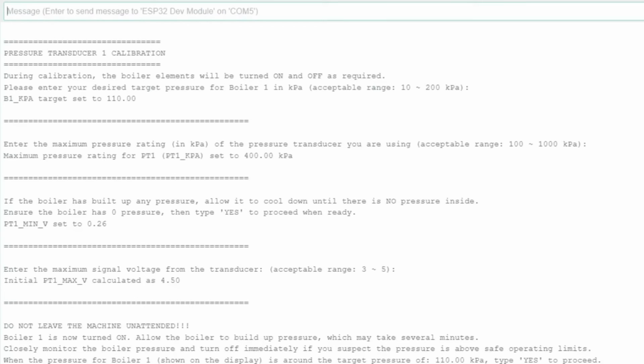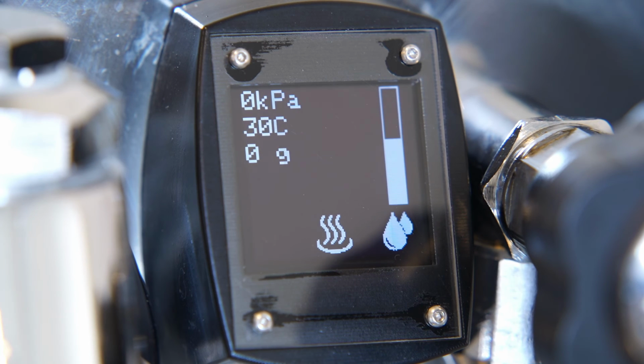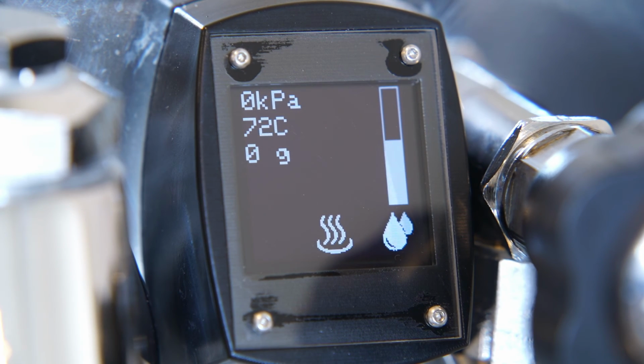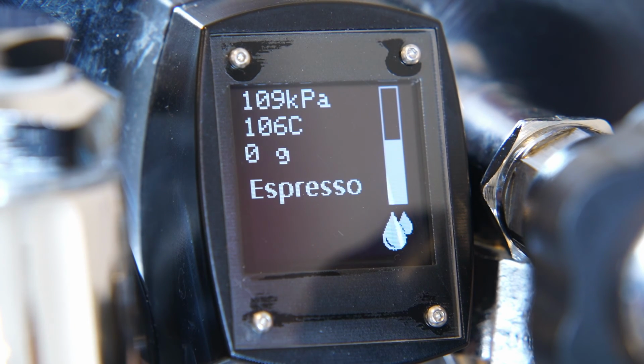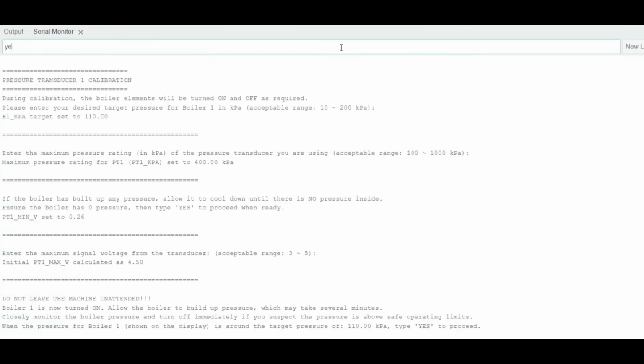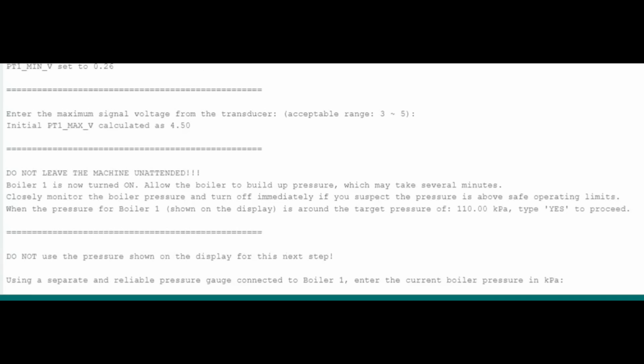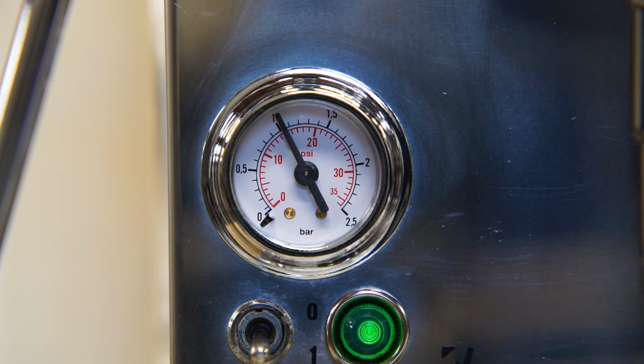The wizard now turns on the boiler element relay. Now we have to wait several minutes until the pressure on the display is close to the target pressure I programmed earlier. With the pressure close to my target of 110 kPa, I can proceed by typing yes. Now the wizard asks me to use a separate and reliable pressure gauge to read the boiler pressure. Looking at the factory gauge on my machine, the pressure is about 1.07 bar, which converts to 107 kPa.